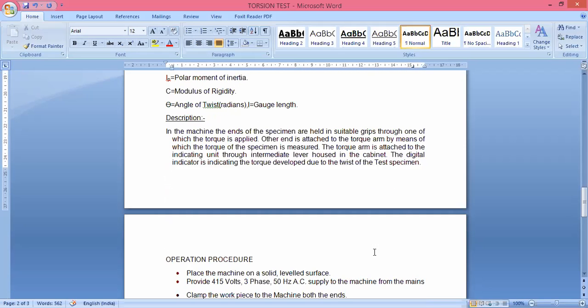Now, the operation and process description of the machine gives us the same thing we have just narrated. The ends of the specimen are held in suitable grips or vices, which I have shown you, through one of which torque is applied. The left side vice is fixed and doesn't rotate, and houses the sensor for determining the torque applied to the workpiece. The right end is attached to a torque drum, by means of which torque is applied to the specimen. The left side is attached to the torque arm, by means of which the torque of the specimen is measured. The torque arm is attached to the indicating unit through an intermediate gear lever housed in the cabinet. The digital indicator indicates the torque developed due to the twist of the specimen.